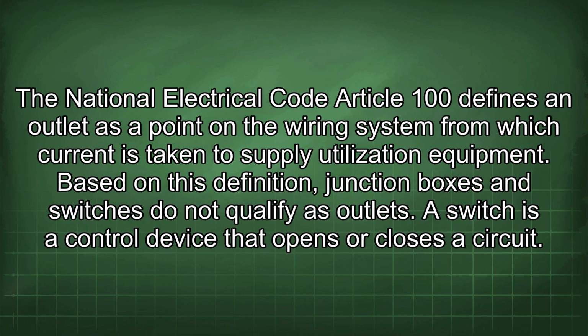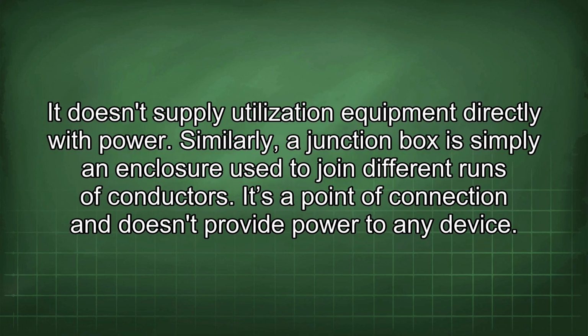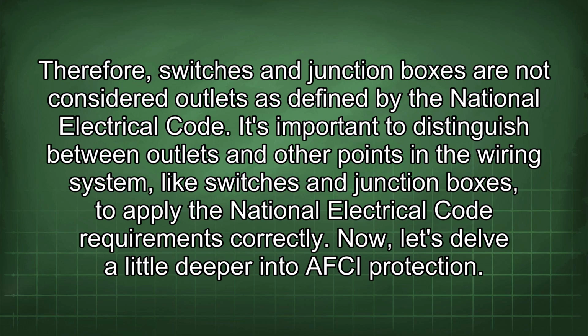Based on this definition, junction boxes and switches do not qualify as outlets. A switch is a control device that opens or closes a circuit. It doesn't supply utilization equipment directly with power. Similarly, a junction box is simply an enclosure used to join different runs of conductors. It's a point of connection and doesn't provide power to any device. Therefore, switches and junction boxes are not considered outlets as defined by the National Electrical Code. It's important to distinguish between outlets and other points in the wiring system like switches and junction boxes to apply the National Electrical Code requirements correctly.